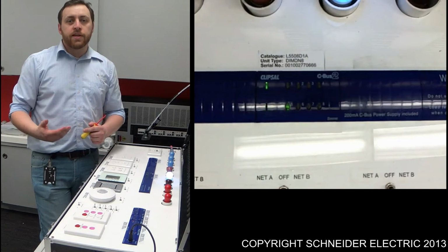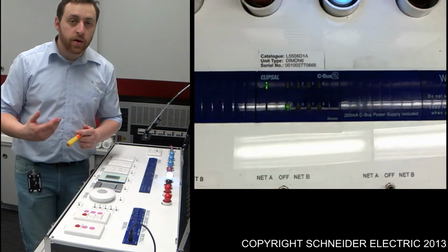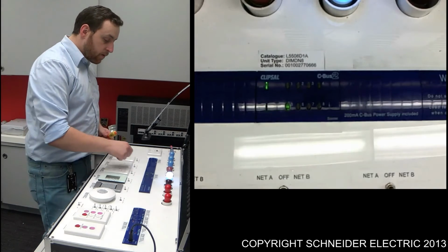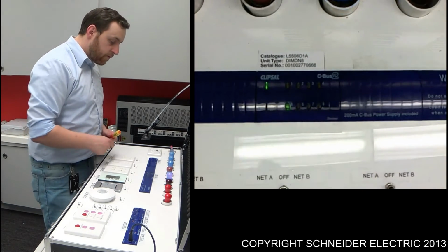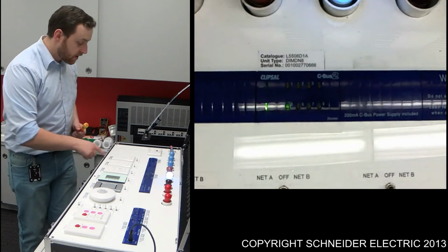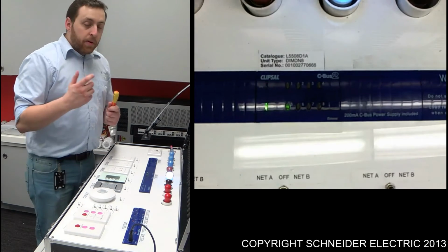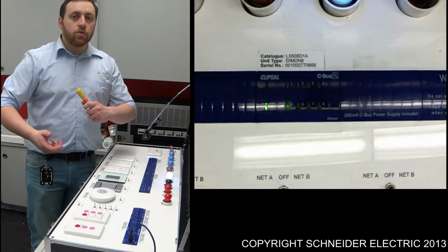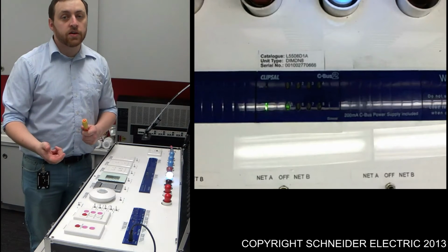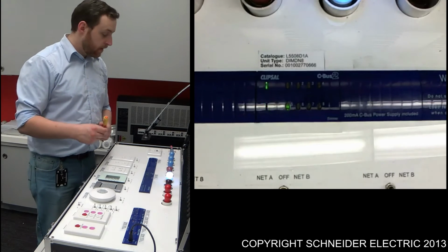Now programming Learn Mode from here is very easy, and let's just say for example you've got a new site, you quickly need to do some functionality programming for the occupants. It's just a matter of selecting the channel, so let's just say channel 5, selecting the key input, which I've just done here. That's just a single gang key input, and depending on whether you want a dimmer function or a relay function: if you want a dimming function, exit Learn Mode on a dimmer. If you just want an on-off function, exit Learn Mode on a relay.